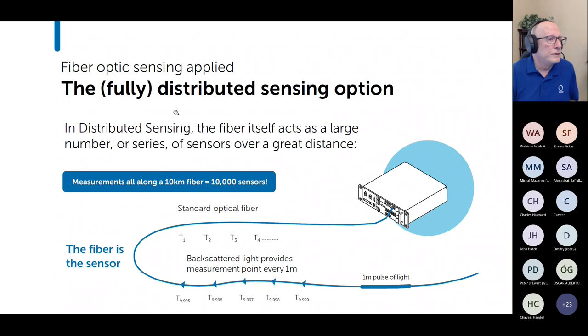The fully distributed sensing option, as I talked about before, you're using the fiber itself as the sensor. And so effectively, you've got thousands of sensors available to you. So if you were doing a 10 kilometer fiber run, you have effectively 10,000 sensors because your pulse of light is going to be on the order of 1 meter. So that's cool.